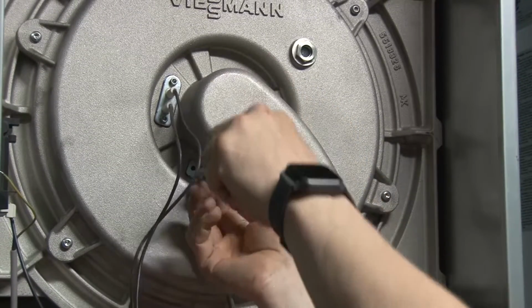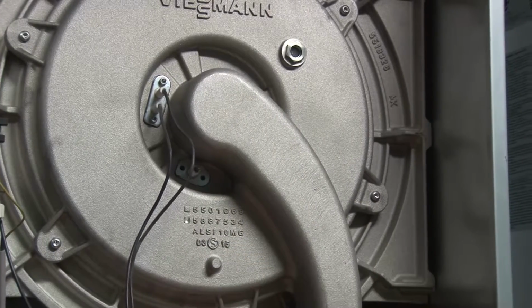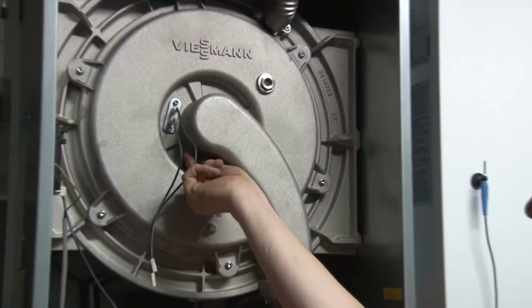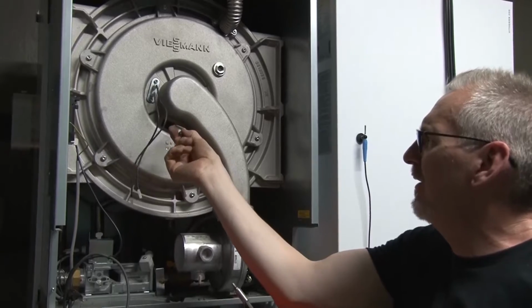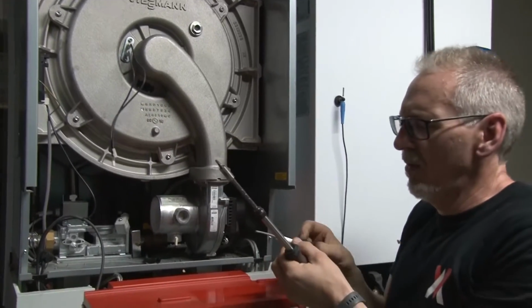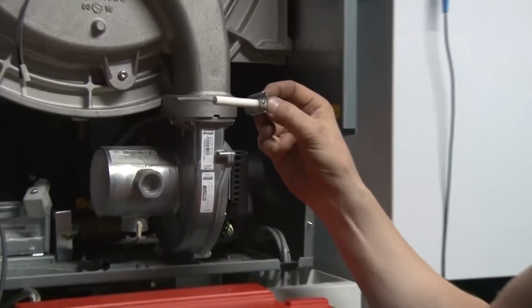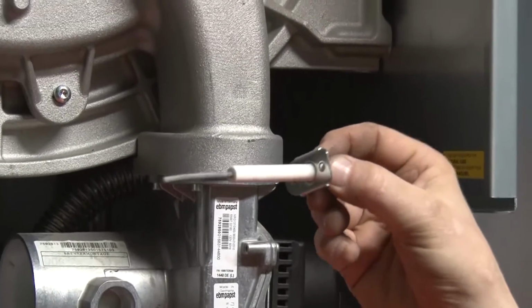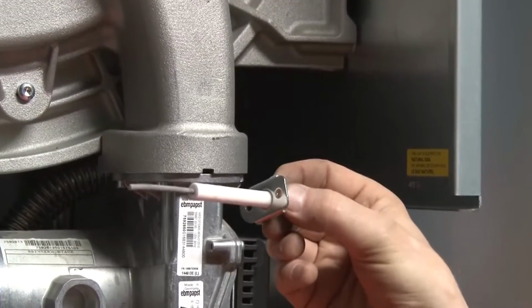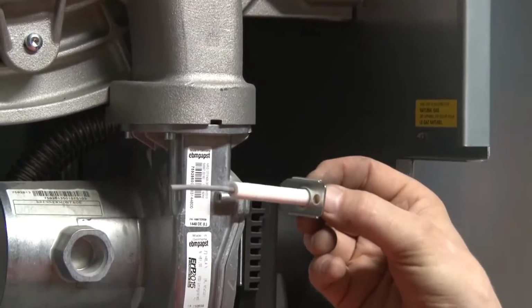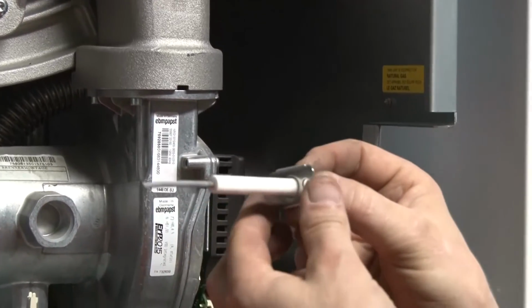So if you're trying to measure that, it's difficult on these boilers because they have a combustion manager. But basically, you're going to get a feedback on this. And of course, the more reliable the flame signal, and this is what the electrode looks like, the better the burner is going to operate, the more reliable it is. As these get fouled up over time, then of course you're going to have a problem because now that flame signal is going to be a little bit weaker.